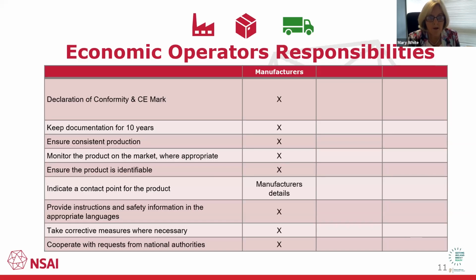So first, here are the manufacturer's main responsibilities. He has to provide the declaration of conformity and CE mark, and this is achieved by completing his technical file. As you can see, he also has to indicate a contact point for the product, and he must keep the documentation for 10 years.